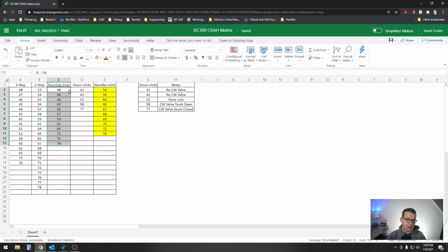Going back to our matrix, these are the units - the only units that can be used in DC300 for redundancy. Really quick on why: because they have a two-way valve and they're not one of the running units. It's as simple as that. Two-way valves are actually beneficial for the type of system we have, that's why we can keep these valved open and operational, to where we can use them at any given time.